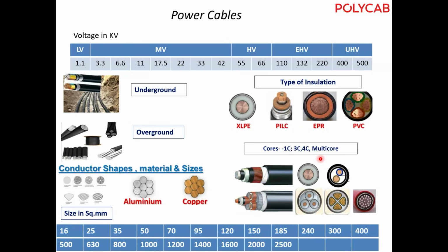Then single core, 3-core, 4-core, multi-core cables. Cables are also classified depending on the conductor shape: sector shape, round shape, aluminum conductor, copper conductor. There are different sizes of cables. It depends on the customer requirements, or on the voltage and the current of the customers. So it starts from 16 square mm to 2500 square mm. These 2000, 2500 are for the EHV grade actually. These cables are required for EHV voltages.